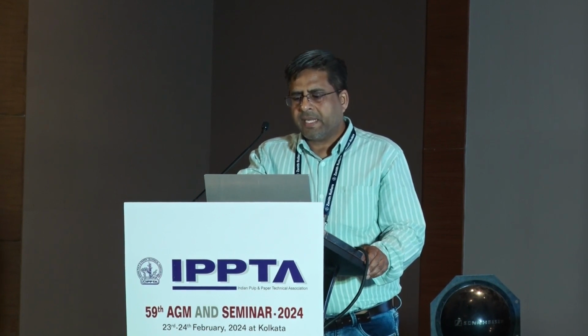Another initiative: we are going to replace all the vacuum pumps with energy efficient turbo blowers. Paper machines require vacuum, which is generated by liquid ring vacuum pumps. The turbo blowers take less power compared to vacuum pumps. There is a saving of power consumption as well as other benefits of efficiency. No anti-scaling chemical is required and the useful life is double that of vacuum pumps.